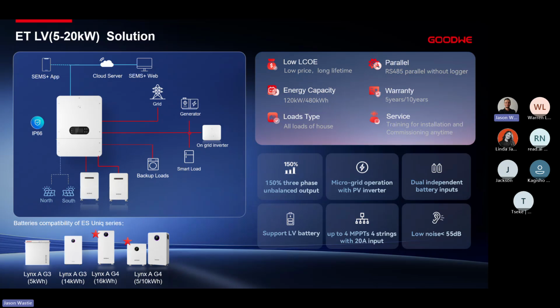With regards to our residential inverters, the ES Uniq as well as the ETLV, we can handle up to double the inverter capacity for 10 seconds for any inductive load or any overload that may occur. So for example, on the 20 kilowatt ETLV, we can handle up to 40 kilowatts for 10 seconds. That does not get taken on the actual batteries itself. That all gets taken on the inverter.